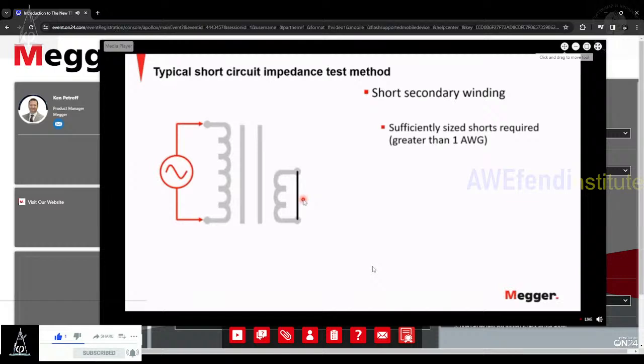and connected to that secondary winding. If you had a short that was too small, say you tried to use the same short that you use for your power factor testing, since that nameplate impedance, that 100 kV transformer that I talked about earlier, that 5%, that means only 5,000 volts to generate the full rated current. It means that that secondary winding is going to generate a significant amount of heat on a short if it's too small. So using that same short that you'd use on the power factor test set may burn up, something that I experienced myself testing in the lab when I didn't quite realize what this percent impedance value meant.